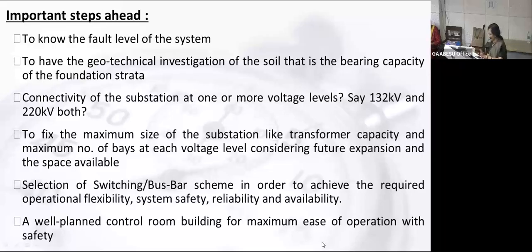Selection of switching scheme, busbar scheme. At this level, I'm talking about, we normally have double main bus 1 and 2 and the transfer bus scheme to have operational flexibility and system safety, reliability and availability. At 132 kV, we can do with 1 main and 1 transfer bus. A well-planned control room building is most essential to have all the operational control from there.